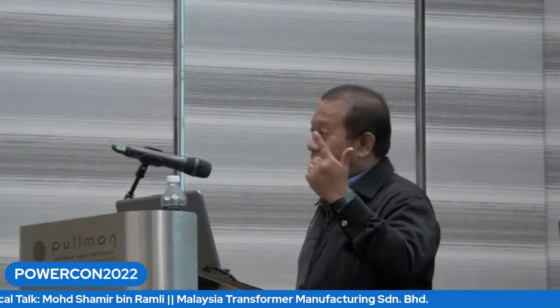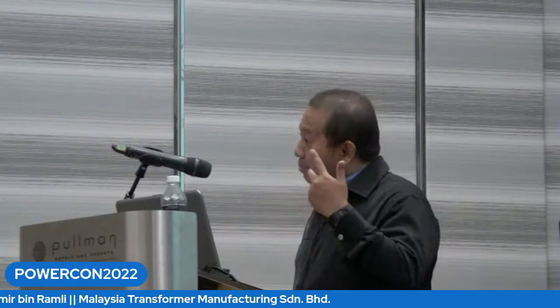Category 1 is the 500 kV transformers, and being 500 kV, it's very crucial to the network. We have almost everything on the transformer. When I say everything, literally, we have online DGA monitoring, visualization in terms of the time feature, and bushing monitoring as well for the 500 kV transformers. When I say practically everything, I mean almost everything.